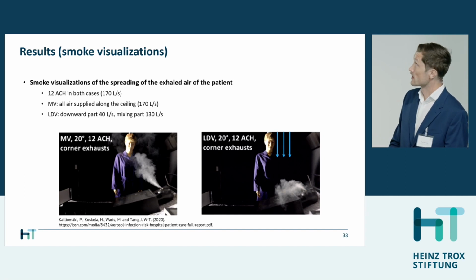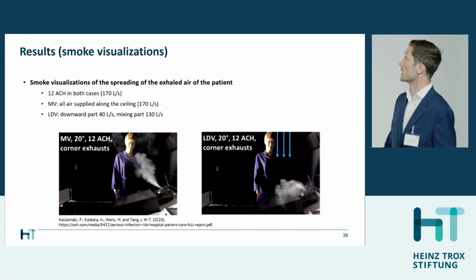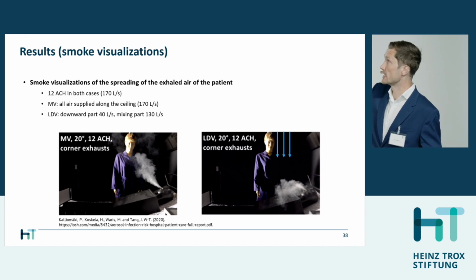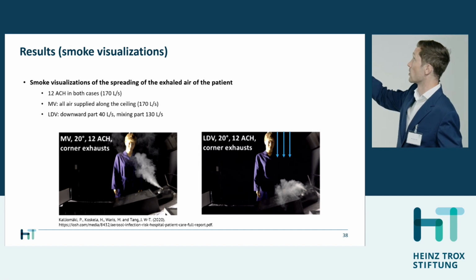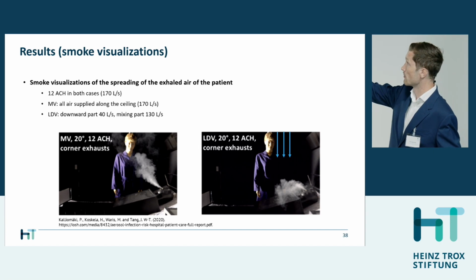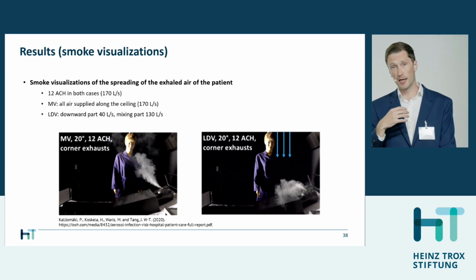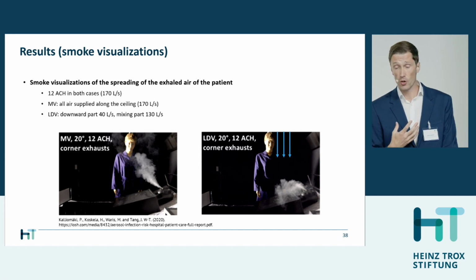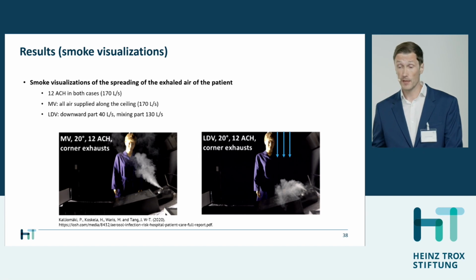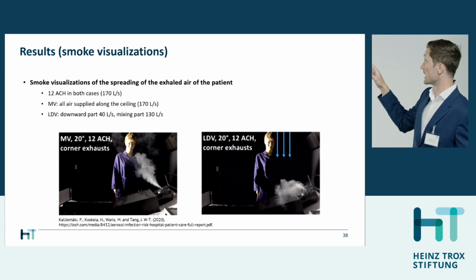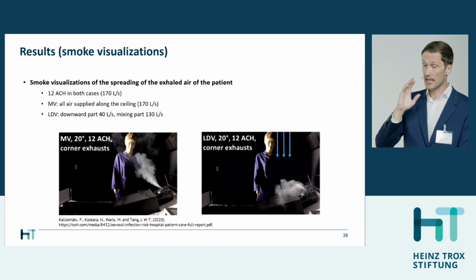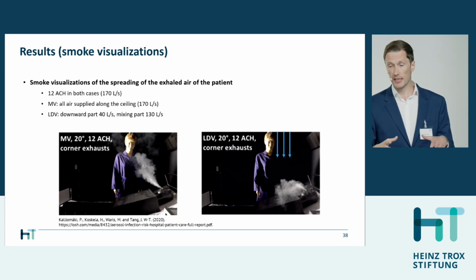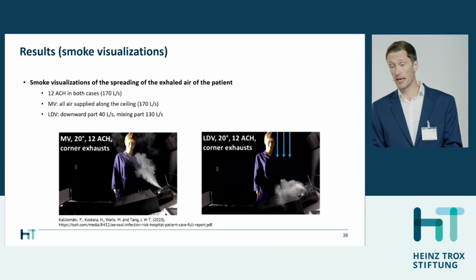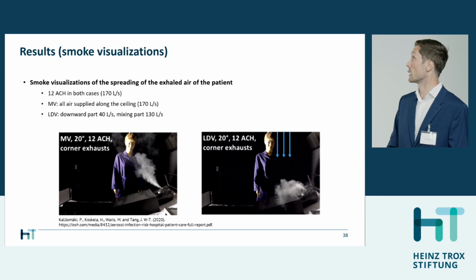So finally, some results. First, the smoke visualizations. Here on the left, you can see the baseline case, the mixing ventilation case with isolation room ventilation flow rates. And on the right, you can see the local downward ventilation case. What you can see directly is that in the mixing ventilation case, the exhaled breath of the mannequin, or the patient, directly penetrates into the breathing zone of the healthcare worker. However, in the local downward ventilation case, you can see that the exhaled breath is directed by the local downward ventilation away from the breathing zones of the healthcare worker and also the patient mannequin.